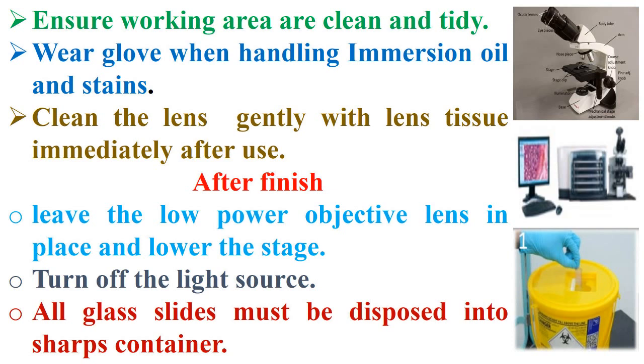For the rules of the light microscope, follow these steps: 1. Ensure the working area is clean and tidy. 2. Wear gloves when handling immersion oil and stains. 3. Clean the lens gently with lens tissue immediately after use. After finishing, leave the low power objective lens in place and lower the stage. Turn off the light source, and finally, all glass slides must be disposed of in a sharps container.